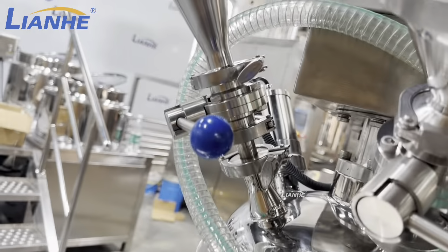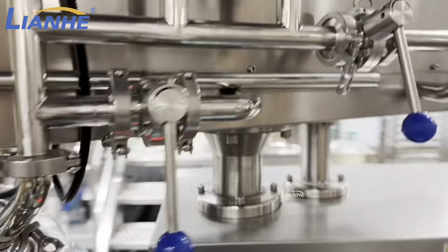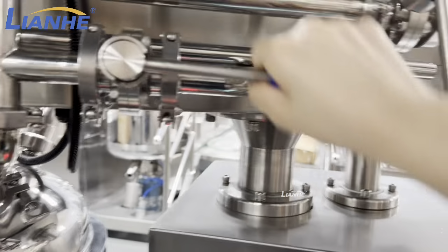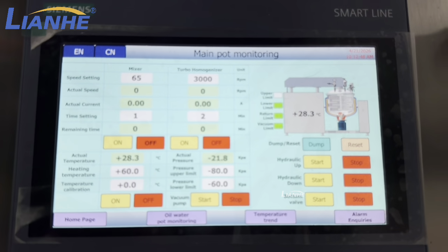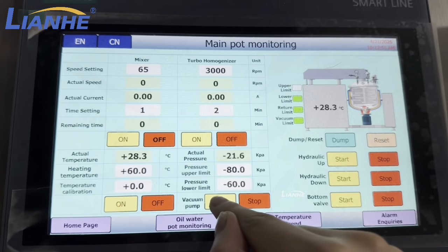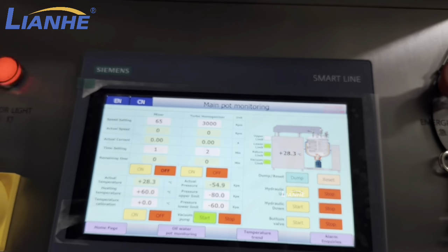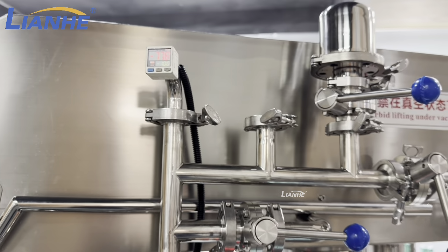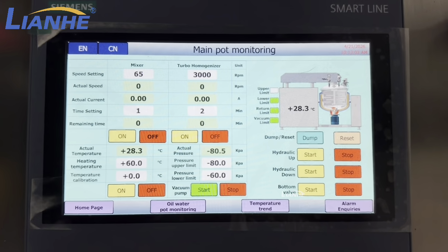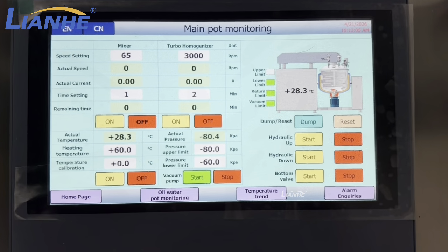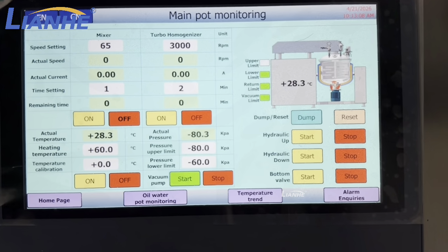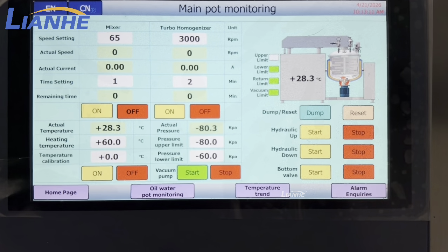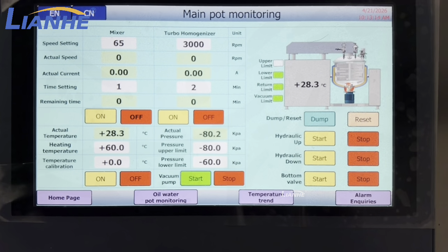And then make sure the other valves are turned off. Turn off all the other valves. Turn on the pressure gauge again. Turn on the vacuum function. You can see now it's minus 80. You can see when the actual pressure is lower than the pressure low limit, like minus 60 kPa, it will restart the vacuum function.